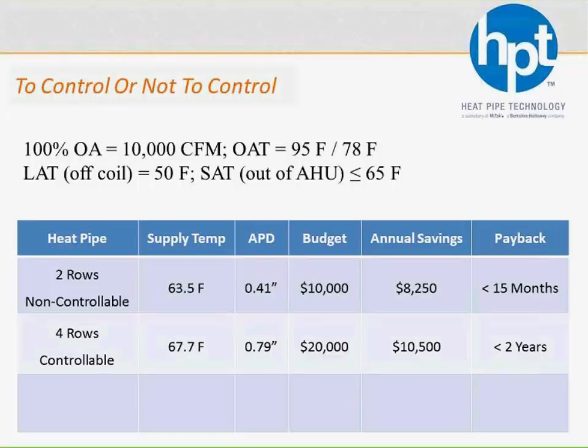If, in this case, 50 degrees is coming off the cooling coil, if there's some time in that year where you're going to need 50-degree supply air, well then by all means you need to make it fully controllable, put a valve on every circuit so that you can shut the heat pipe off completely. But let's say that you're always going to want some reheat. Let's say that you'll always want at least 55-degree air coming out of the system. Well then why would you put valves on every circuit? Let's just say we put the valves on half the circuits.